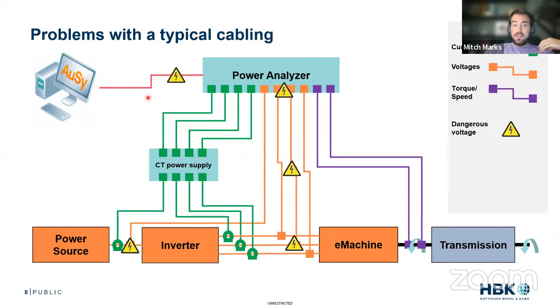And if there's a copper connection to the automation system or to your host PC, now we have a safety issue that involves humans. So we have both the safety of the instrument and the safety of the person, if you're connecting it to a PC — and not all instruments are rated to that CAT level.